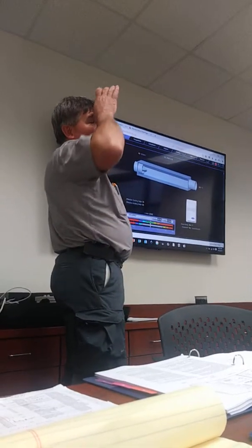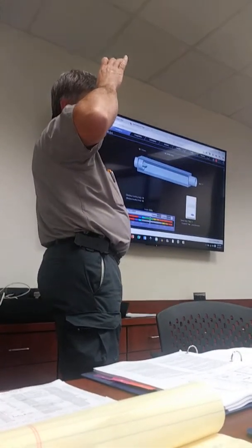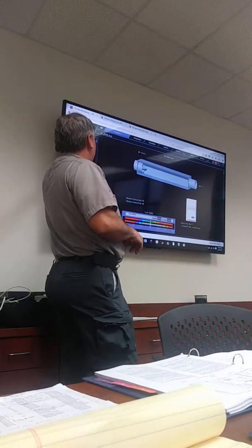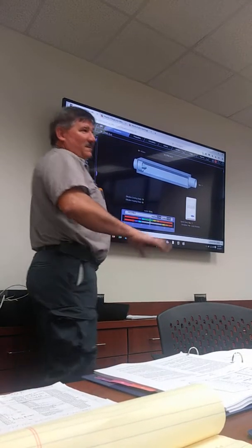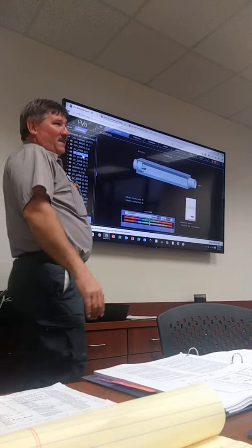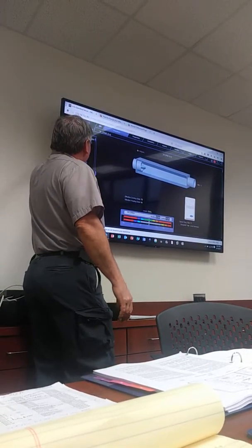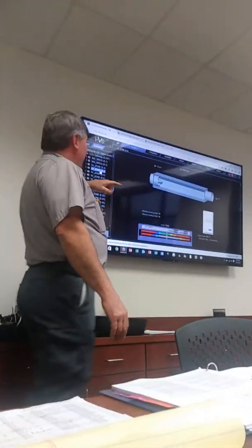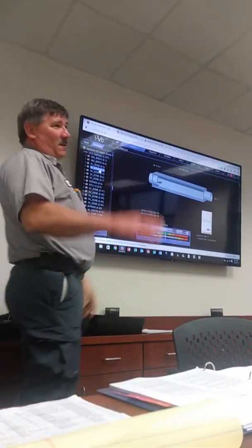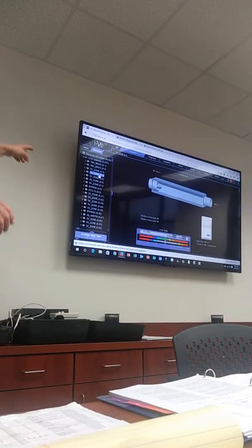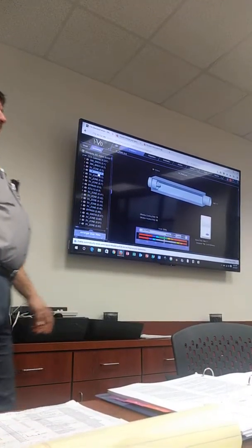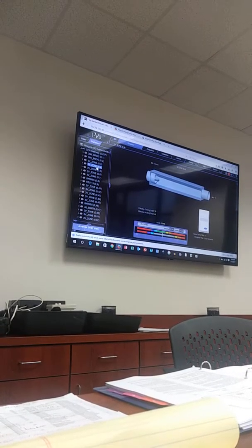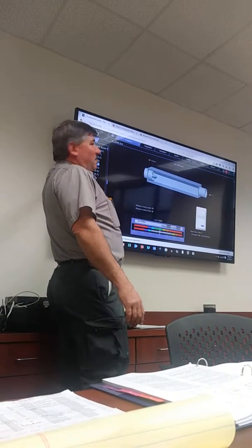Usually what we'll do if they duct one of those computer rooms or something small that's calling for cooling all the time, we'll take that address and put it out in left field, like down here at the bottom somewhere, because then this guy doesn't see it. If it's not in its sequential order, this guy doesn't know it's there. So we'll take that zone. In this example, we would take 03 and address it at whatever, 0200, out there in left field by itself. And then tell this guy you only have 4 zones instead of 5.